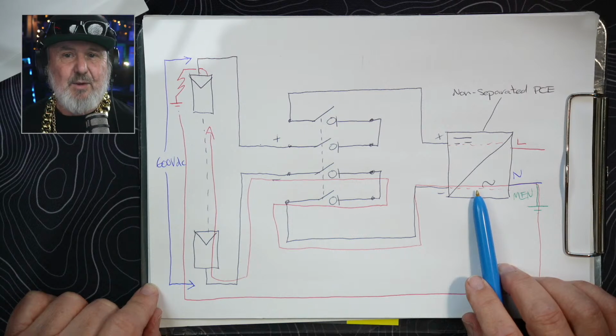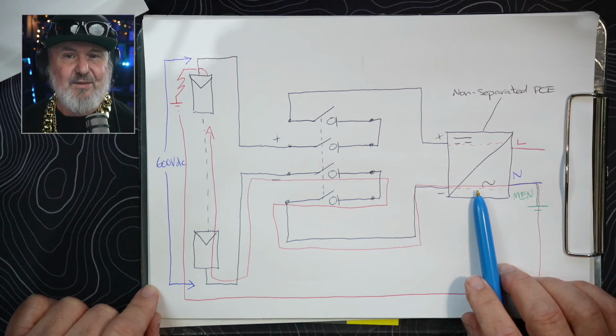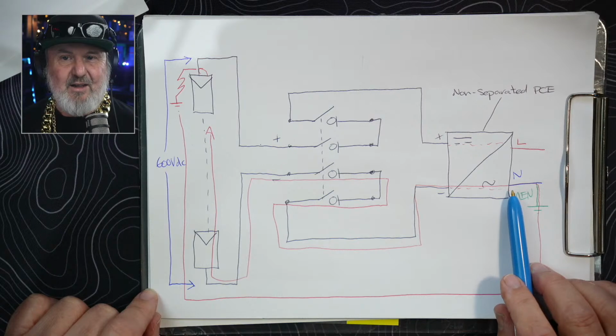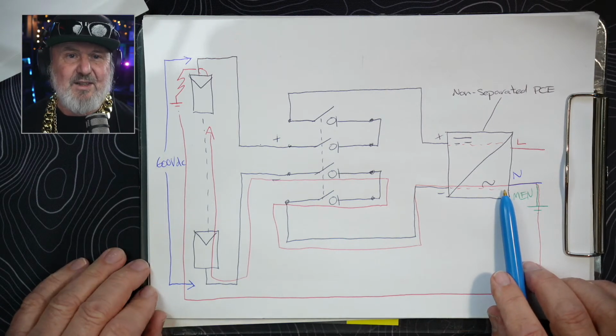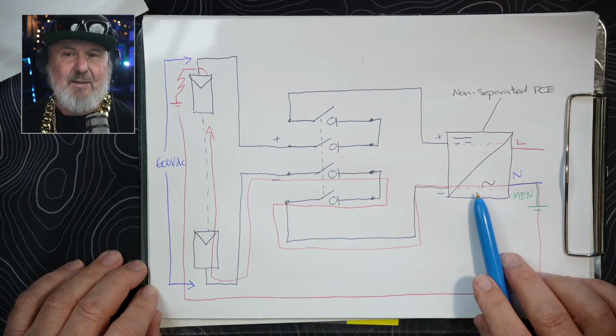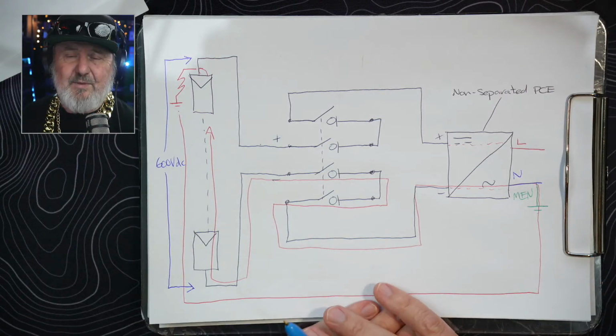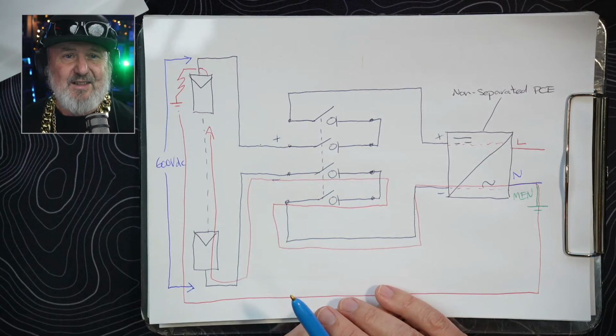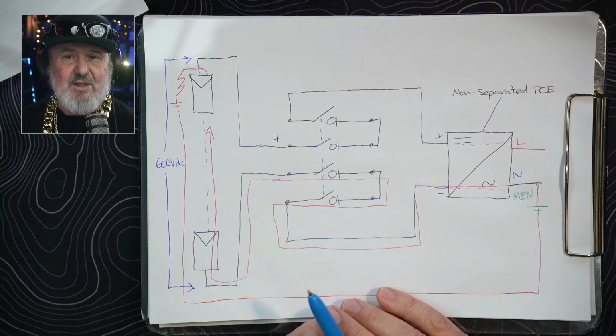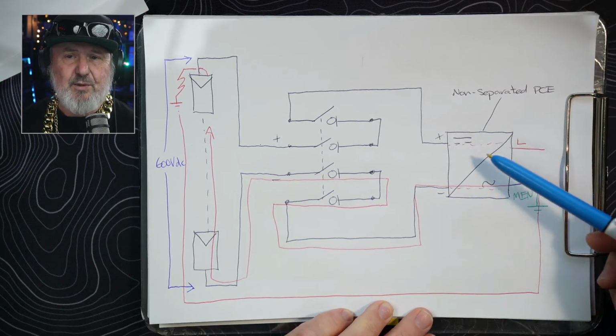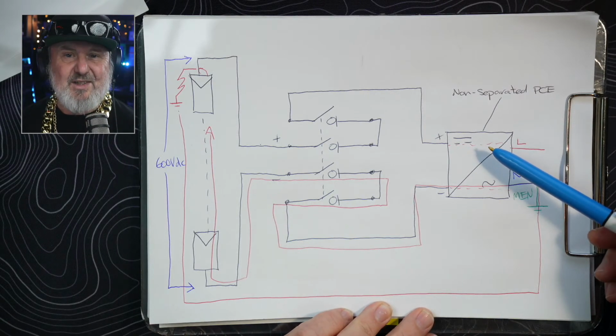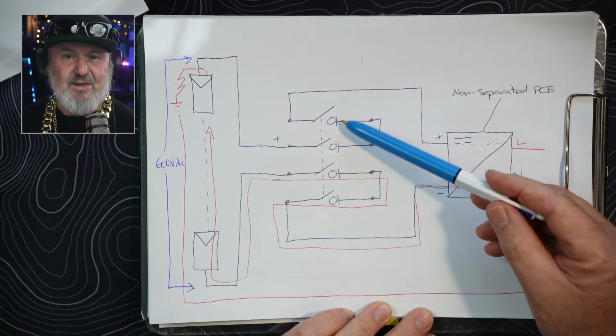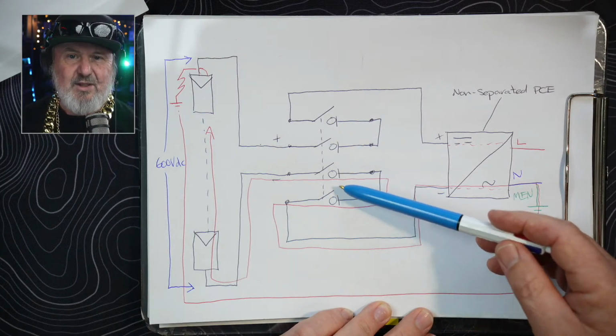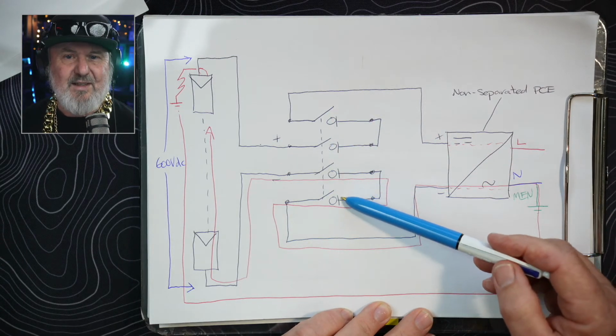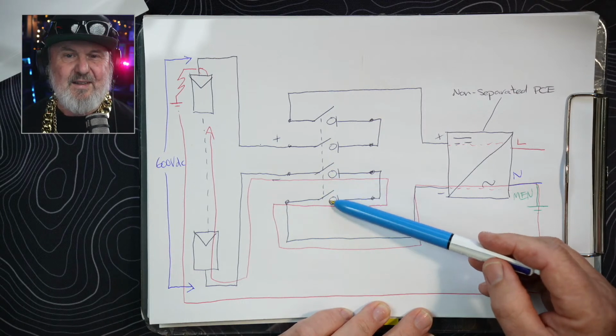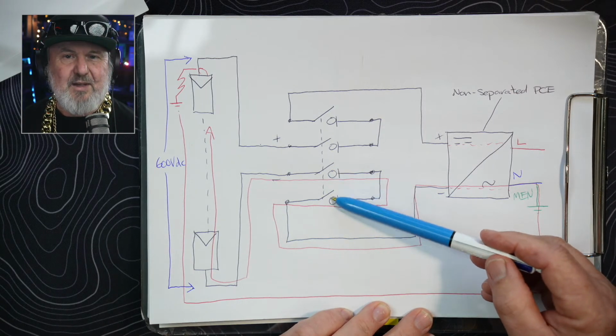But if you get a hard bolted earth fault, it generally takes out the inverter. And they fail in pass-through. It's only semiconductors in there. They just burn out. So you end up with a melted bit of electronics that's just conducting DC through to the AC side. So we need to take this inverter off the wall and replace it. But that means we need to be able to isolate it. So we go to operate this switch here, and you'll notice that even though it's got 4 poles, in this case, only 2 of them on the negative leg are going to interrupt the current.